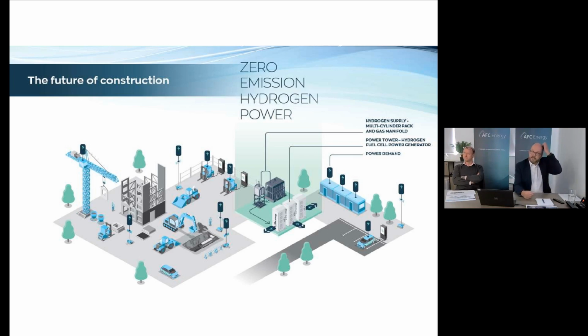There's an interesting statistic on the crane you can see there. We've not powered a crane yet, we're in discussions with a few crane operators, but a crane traditionally has a 200 kilowatt or kVA generator at the bottom. At night time, when the operator goes home, you still have that little light at the top requiring power. Overnight, that generator is reduced in output, but it can only go down to about 30 kilowatts, meaning you're using approximately the power needed to run 60 UK homes just to run a little light on top of a crane.